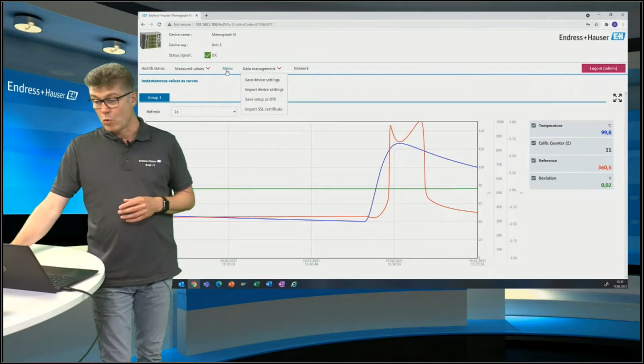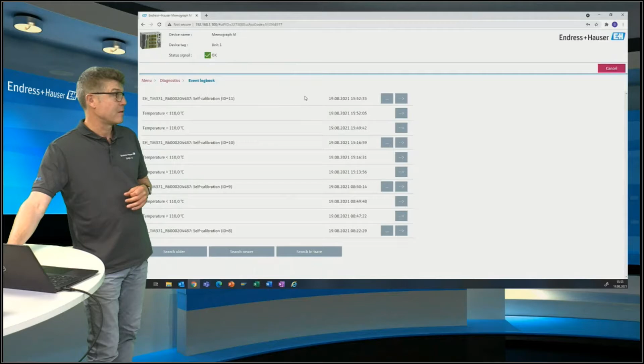And I can also have a detailed look at the calibration event. Going to the calibration event log, we see here at 15:52 we had a calibration event. This is local time. We have 3 minutes later now, and I can go here and see that at this time we had a calibration. This is the serial number of this sensor. We have the reference temperature, which is 117.78. The measured temperature was 117.80. So we have 0.02 deviation, and the tolerance, which is stored here, is 0.8.